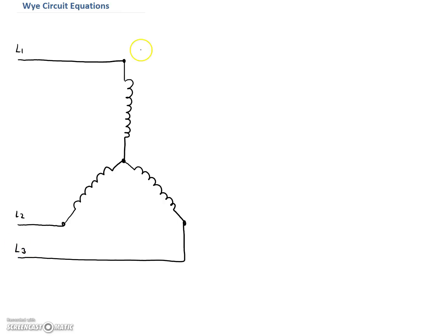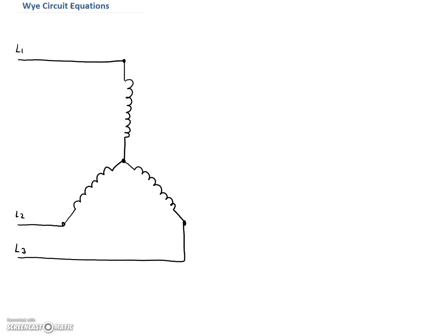I'm just leaving room here so I can put all of my equations for a Y circuit. We're going to look at this and ask: is this a series or a parallel circuit? Well, here we're saying that this is probably the secondary of the transformer, so the current is going out of the transformer. At that point, it looks like there's only one path for that current to flow — going from Line 1 to Line 2, there's only one path for current to flow. Whereas in the delta, there were two paths. So think of Y circuits from now on as a series circuit. In a series circuit the current is the same, and that's going to help us with the equations.